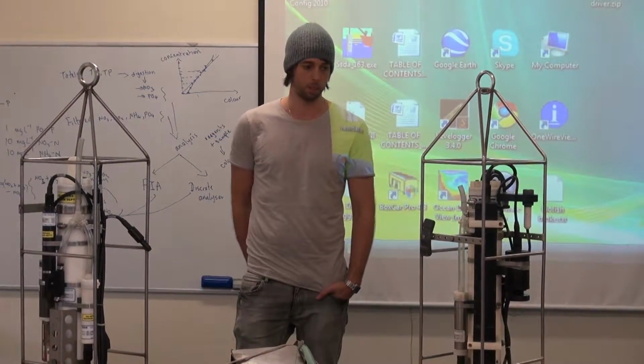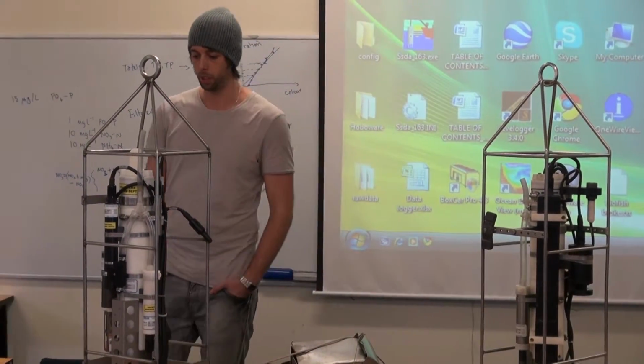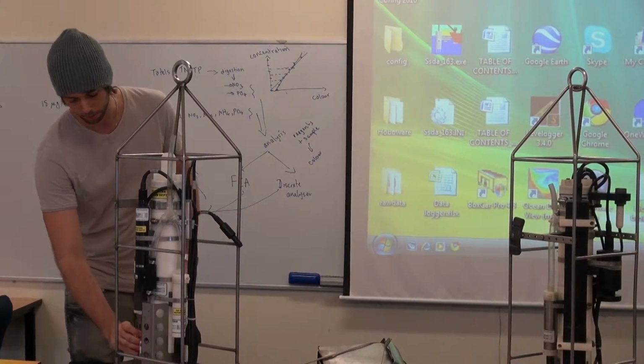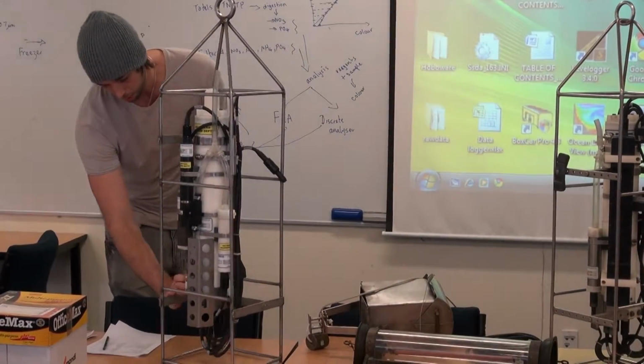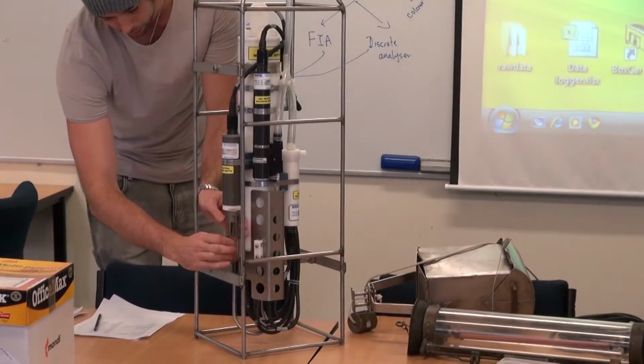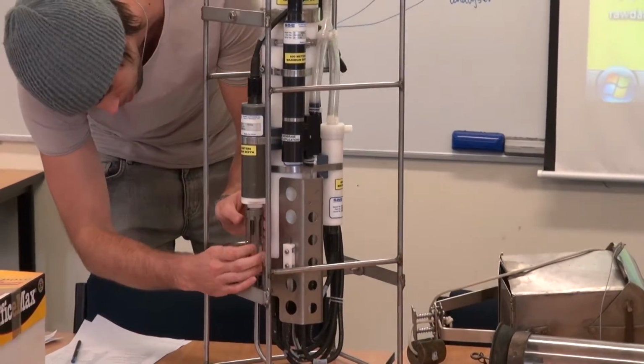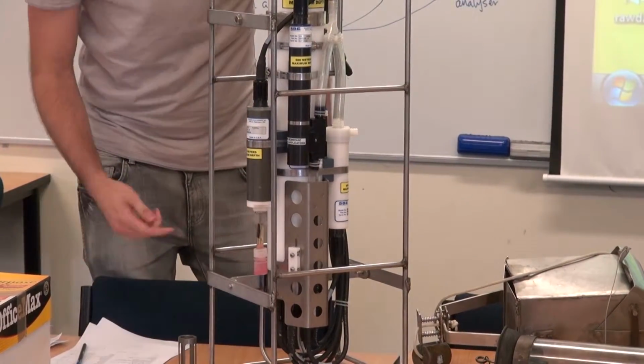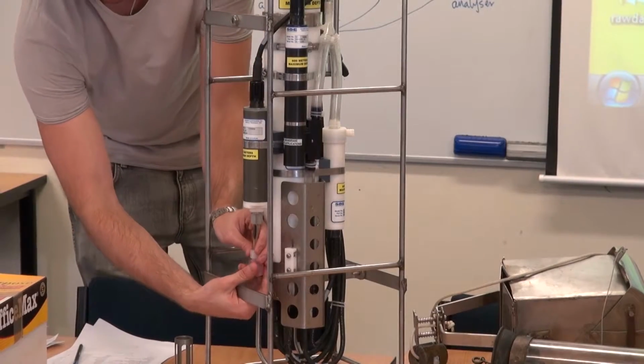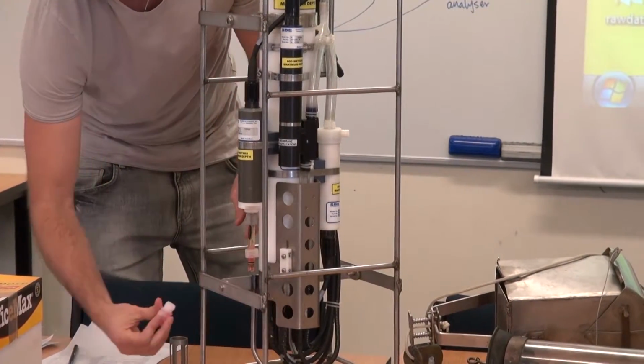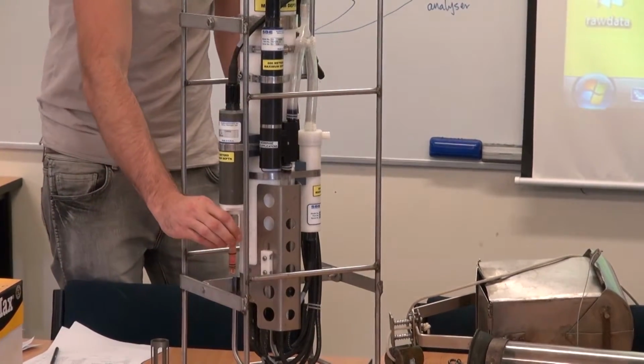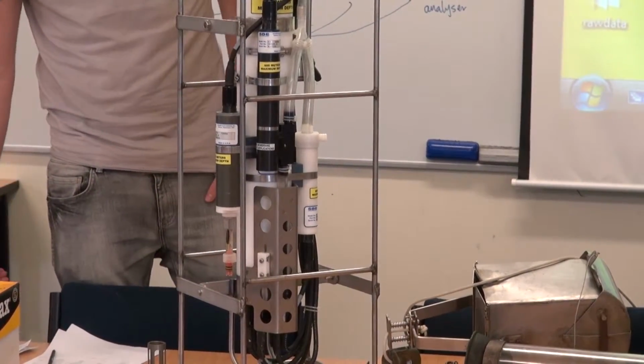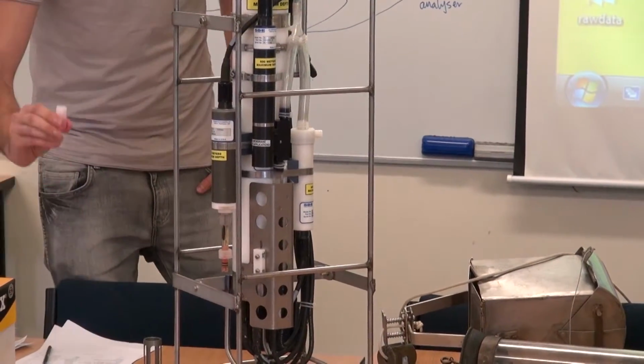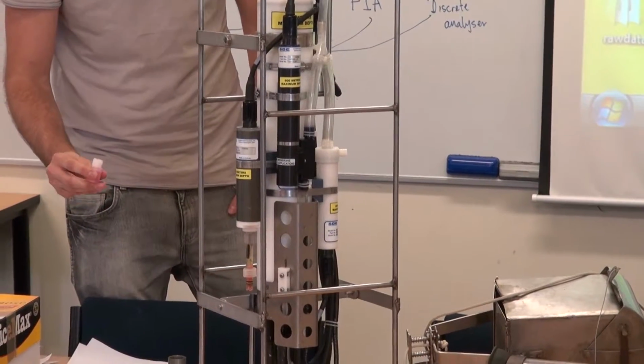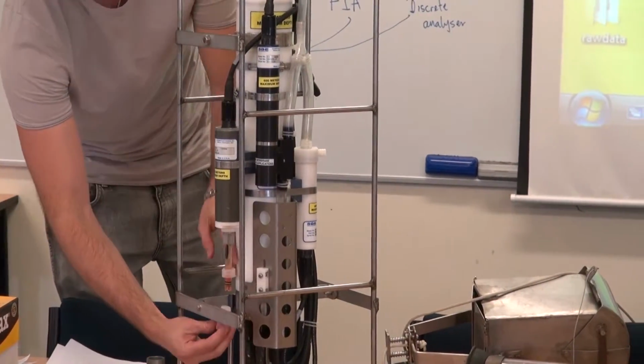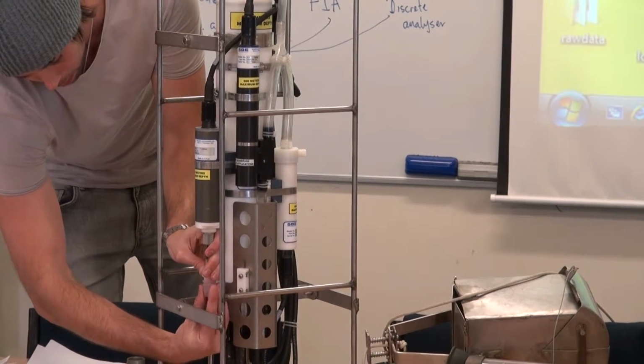Where else to start? So in the field, obviously, first thing you need to do is make sure you've got all your caps off. And we just took the caps off on that one. The pH sensor is a little bit trickier. There's a cage over it here. As with the other pH sensors we've seen, it gets stored in a little bit of buffer solution there, so take that cap off. You can leave this, it's got an O-ring underneath it, so it won't slide off. You can leave that on there to do your profile. Make sure you don't spill this or lose it. It's often ended up stored dry, and that's not really what we want. So when you're done, chuck it back on.